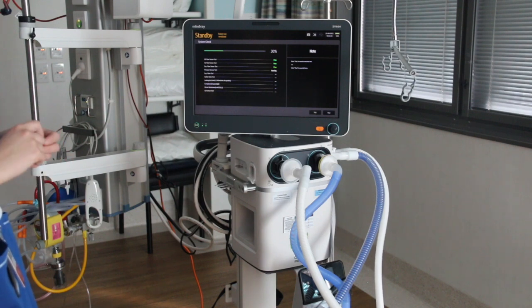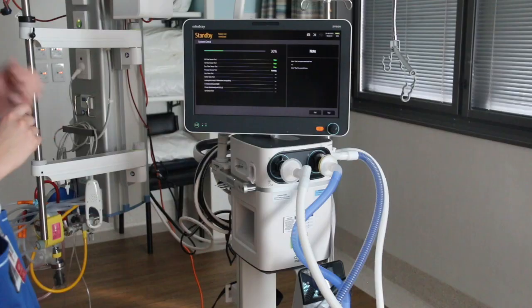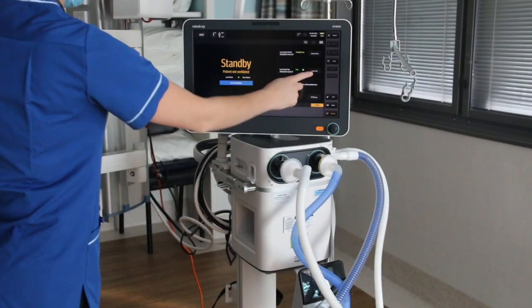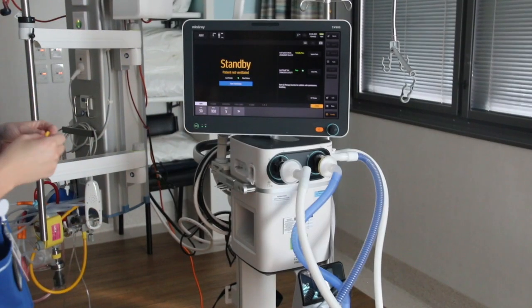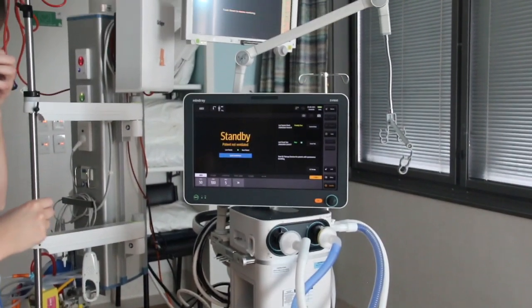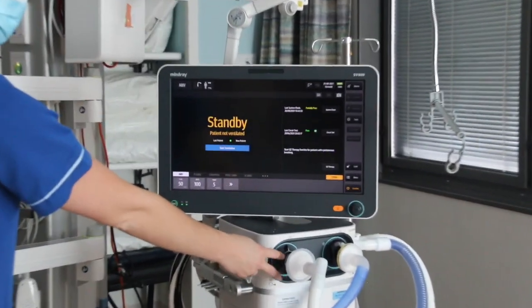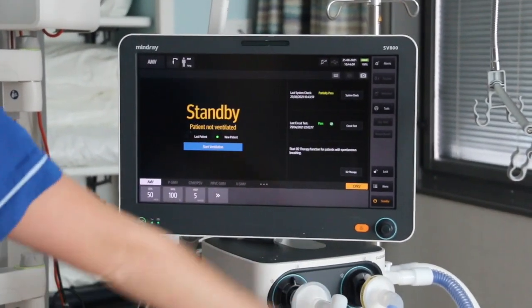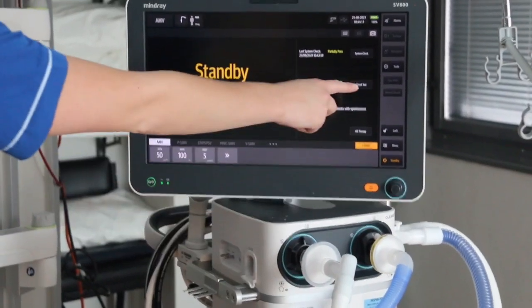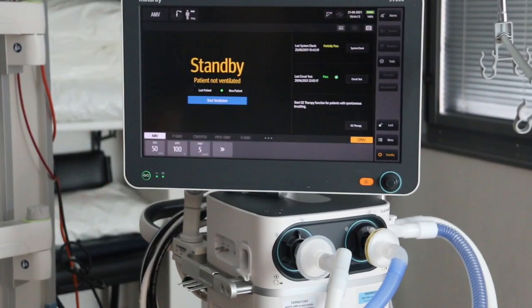If you need to change the tubing in between patients, there's another option on the main screen. Here, for circuit test, if you just need to change the circuitry in between patients but you're not changing your exhalation valve flow sensor combo, if you're just changing the circuit, you can do this shorter circuit test here, which only takes about 30 seconds.